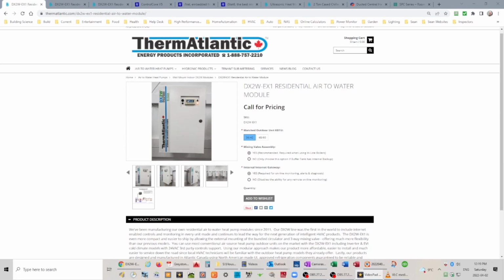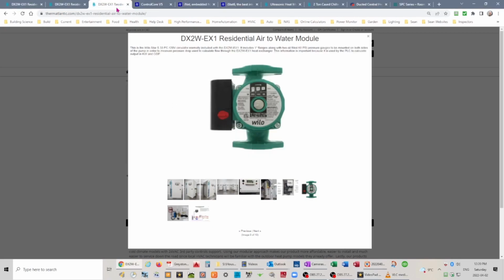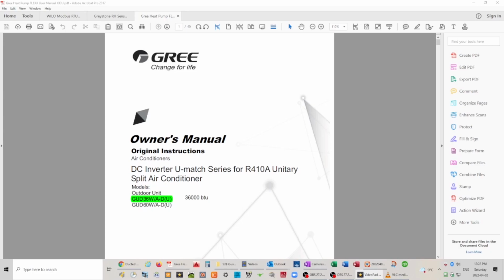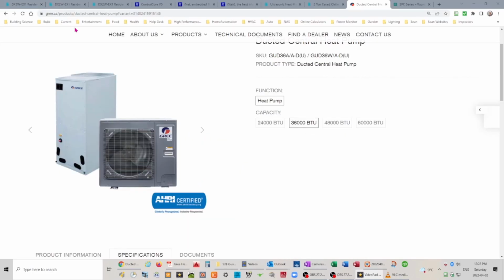The module is from ThermAtlantic, and it allows for communication and control via the Modbus protocol, which I'll talk about in a bit. It is also provided with a Wilo Star circulator that is installed on the circuit between the buffer tank and the DX2W module. We have then mated this with a GREE heat pump. It is a DC inverter, 36,000 BTU heat pump, 24 volt. And this is a prototype mating of these two units.